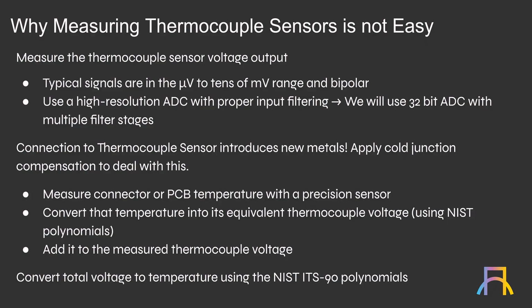Okay, let's talk about why it's not easy to measure thermocouple sensors. A thermocouple signal can be as low as microvolts and as high as the tens of millivolts range. But we need that resolution into the microvolts to make these measurements and make them accurate. Not only that, the signals are bipolar. That means the voltage values, depending on the type and the range you're in, could be positive voltages or could be negative voltages, right? So how do you measure that?